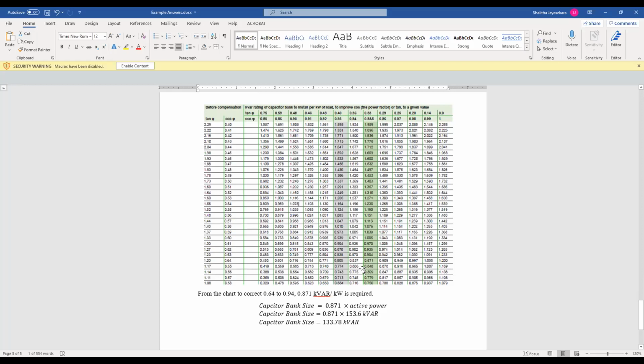So please remember this, because I think this is not included in the lecture. This is how you are going to find out the required compensation per kilowatt. Remember that this is the required compensation per kilowatt. So if you need to upgrade your system from 0.64 to 0.95, you need compensation of 0.871 kVAR per kilowatt.